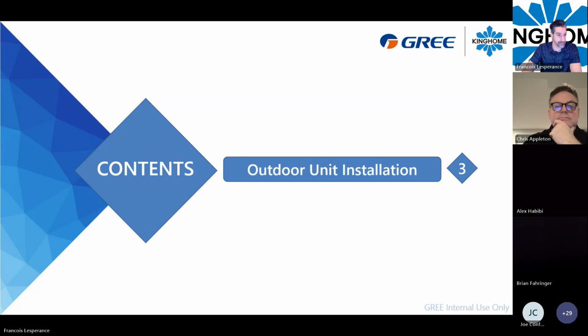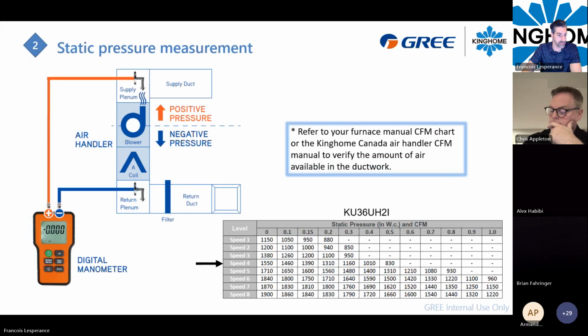Yep. Hi, sorry to interrupt you there. We do have a question in regards to the airflow. How much airflow per ton are we using for these GREE heat pumps? Well, the airflow is about the indoor unit. So what are we recommending per ton for GREE heat pumps? Well, everything around 325 to 400 CFM per ton. Normally in air conditioning, we are using 400 CFM per ton. This is a rule of thumb. And for heat pumps, we are using a little bit more airflow than conventional air conditioning. So if we use from 325 to 400, will they work nicely? Yes.